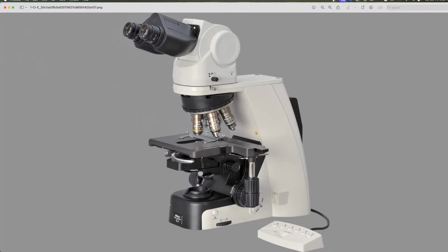Achromats are objectives that have corrections in 2 of the fields of the spectrum, the areas of the spectrum that represent red and blue. They are corrected in those areas, but not in the central part of the spectrum. If you want that, you need more elements in the lens. They're much more expensive, and they're called apochromatic. Apochromatic objectives are the ones you want to go after, and they are corrected across the board, so you get the least color fringing and the best performance. So that's one of the key features.